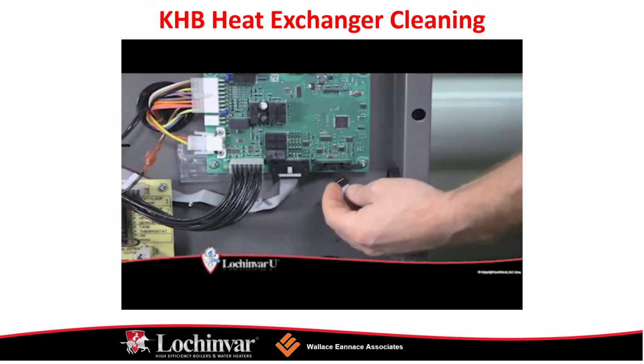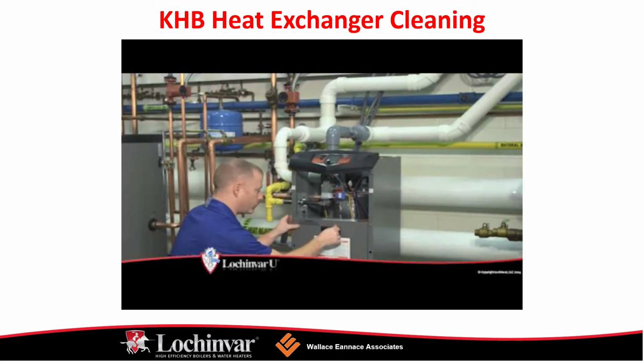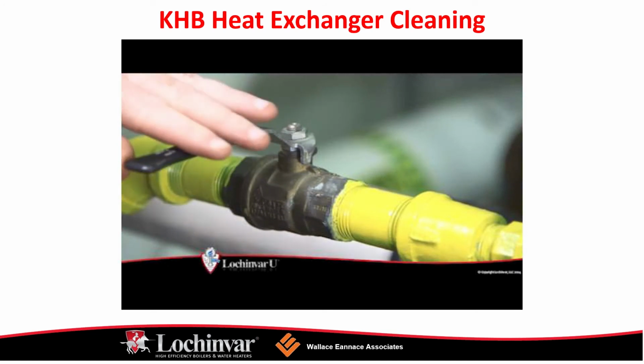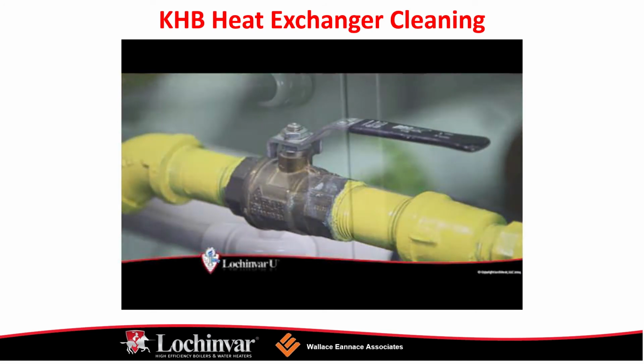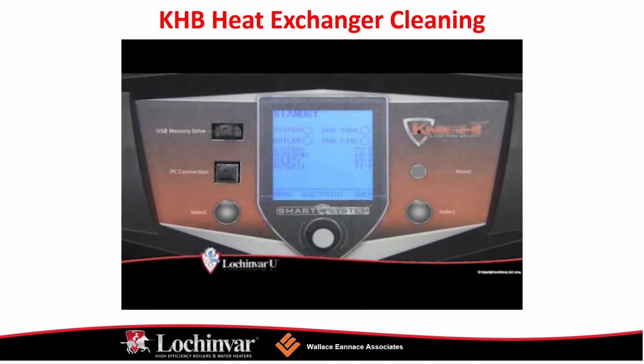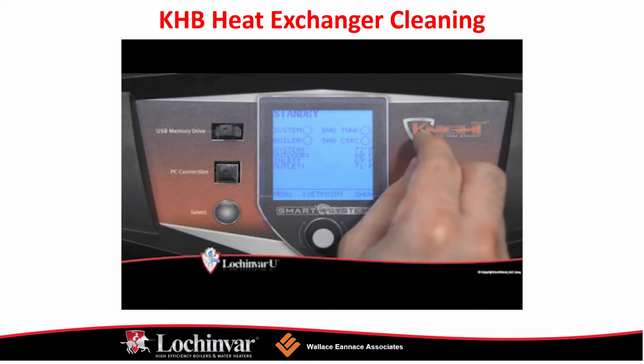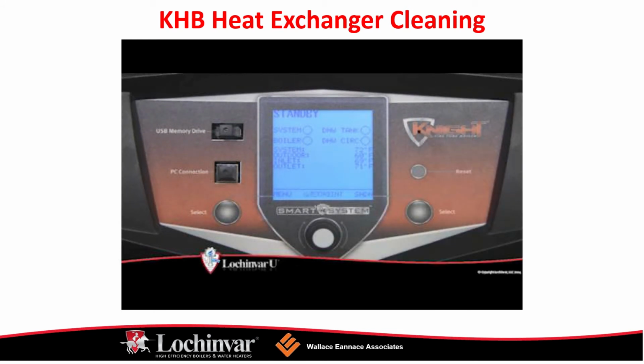Once the cleaning process is complete, reconnect the condensate drain line to the condensate trap. Then, replace the heat exchanger door and secure it to the heat exchanger. If equipped with an air shutter, replace the shutter and then replace the combustion air blower and Venturi to the heat exchanger door. Then tighten the union on the Venturi. Now tighten the band clamp securing the air inlet to the Venturi and reattach the rubber hose to the air intake pipe. Reconnect the wiring from the flame rod, spark igniter, and ground terminals to the heat exchanger door. And reconnect the two wiring harness connections to the combustion blower.